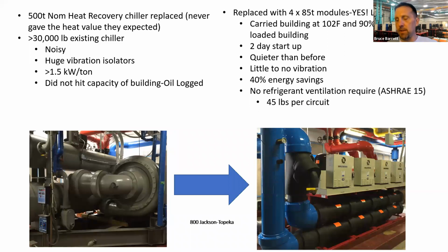Real job we did in Topeka, 500-ton change out. Granted, it was a very, very old chiller, it had oil in it. It was very oil logged, lost a lot of capacity over the years, given the amount of charge that would migrate to the condenser side of the machine. They'd continually have to add more oil.